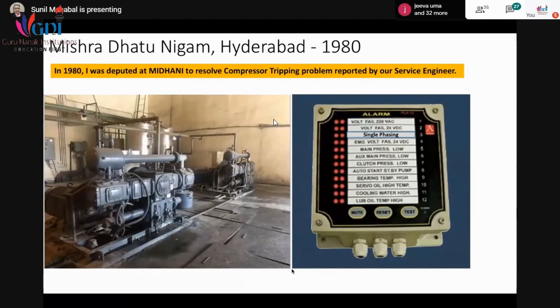And then once it tripped in front of me, the reason I got was the annunciator was showing single phasing. Then the reason was known, that it is tripping because of single phasing. But there was no obvious single phasing. I hope everybody knows what single phasing is. Single phasing happens when a three-phase motor receives only two phases.